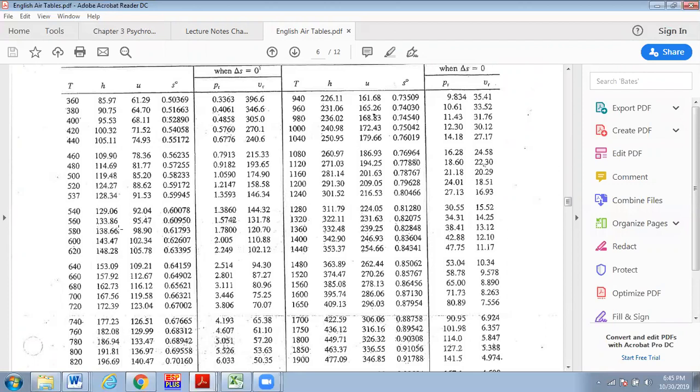Okay, so if I take 133.86 and subtract off 109.9, I get a number I can compare to the Psych chart. I'm adjusting the reference, okay? 133.86 minus 109.9 is 23.96. So it's just a smidgen under 24.